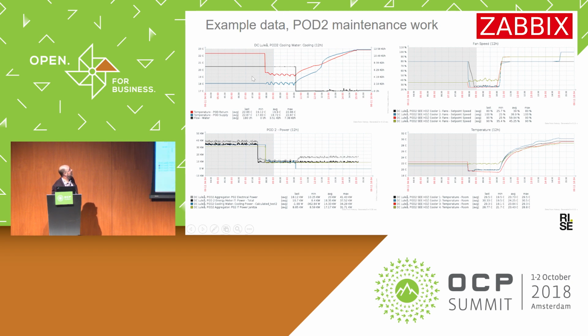This black line here is the water flow. We turn the water flow off here into the data center because we're going to do some maintenance. We still had some systems on, so the temperature was rising, and as the data center got warm, the flow and the return got to the same temperature. So that just gives you an example of the kind of output.